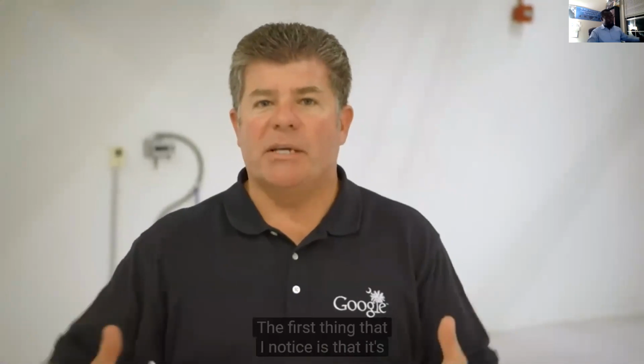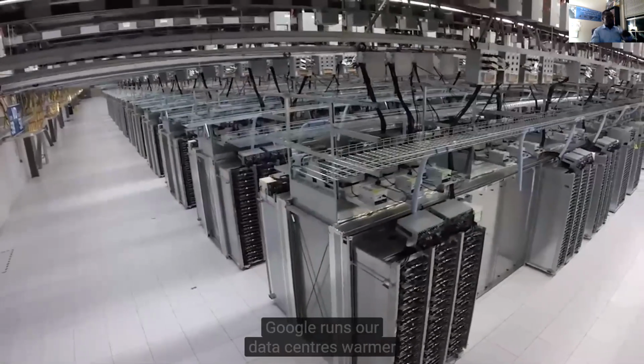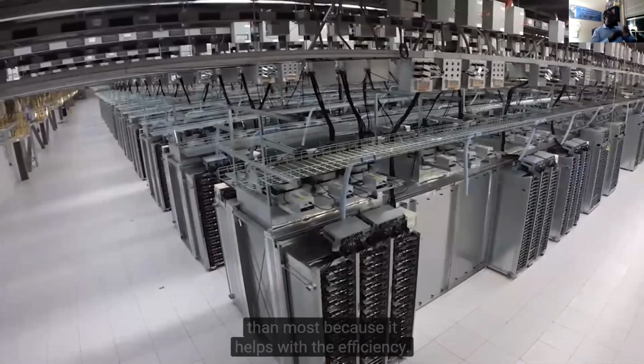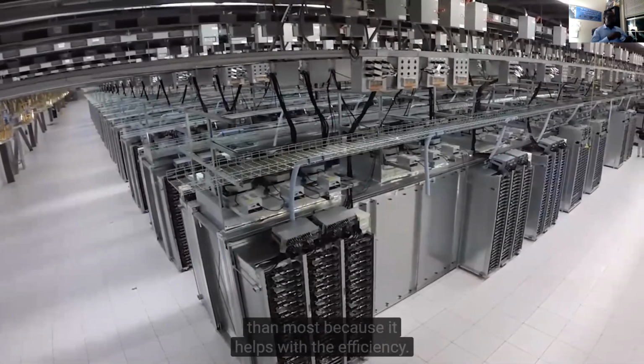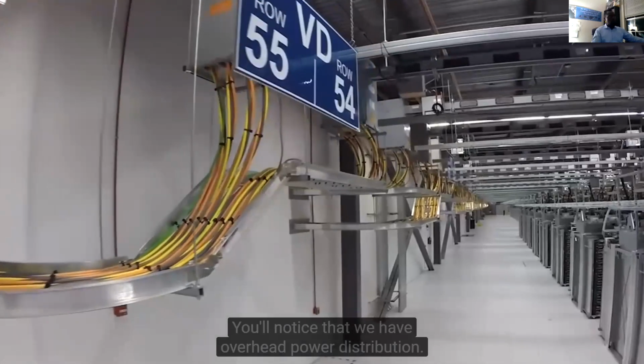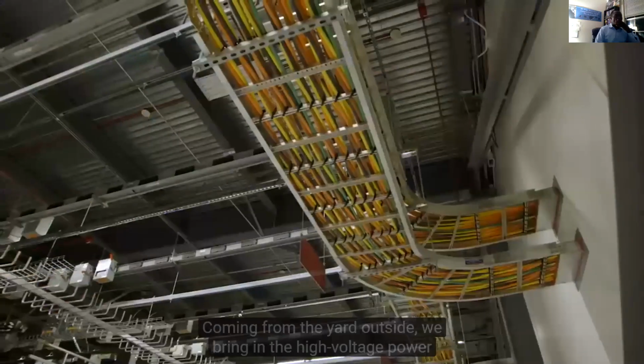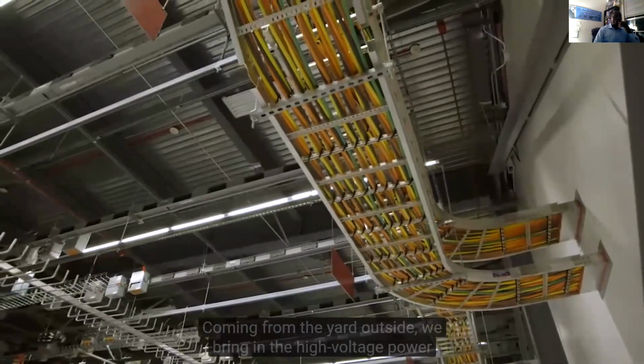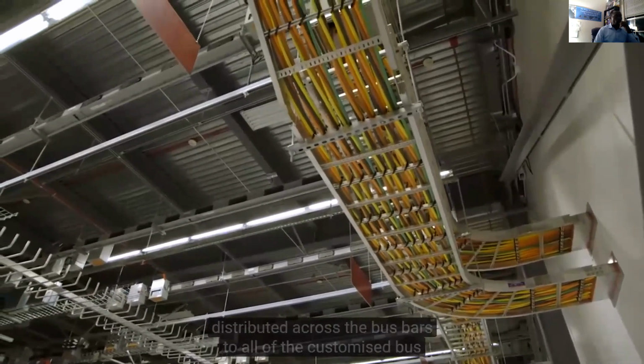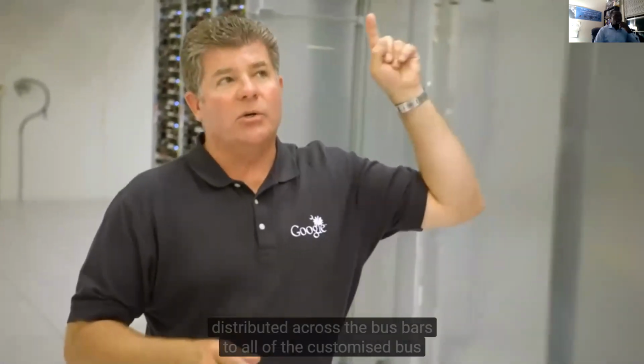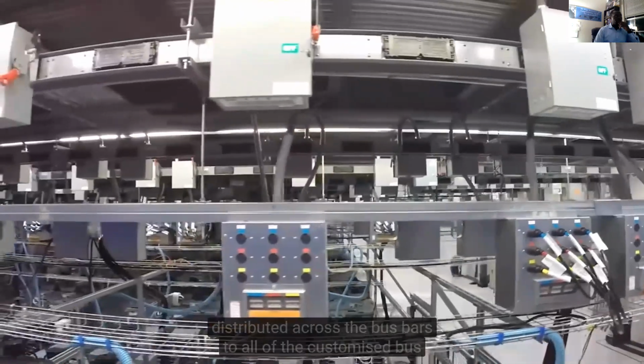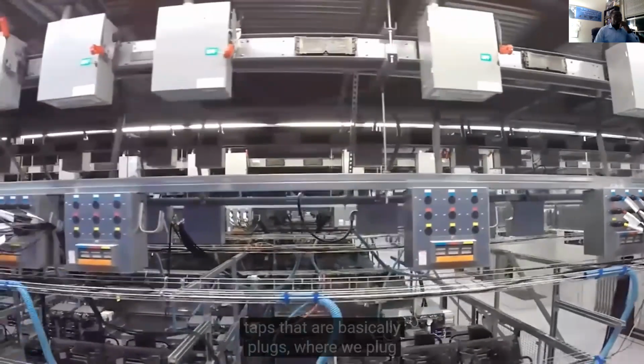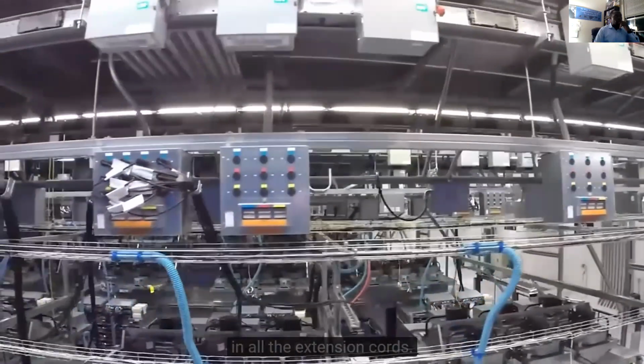First thing that I notice is that it's a little warm in here. It's about 80 degrees Fahrenheit. Google runs our data centers warmer than most because it helps with the efficiency. You'll notice that we have overhead power distribution. Coming from the outside yard, we bring in the high voltage power, distribute across the bus bars to all of the customized bus taps that are basically plugs where we plug in all the extension cords.